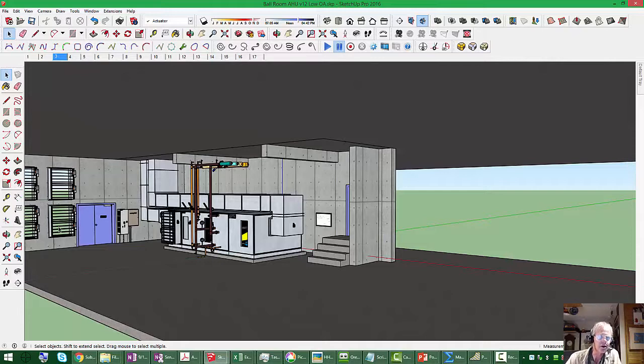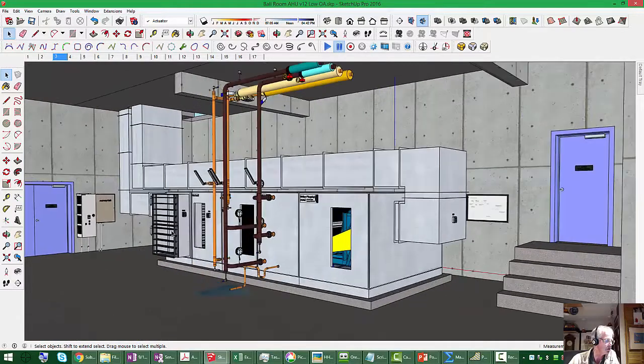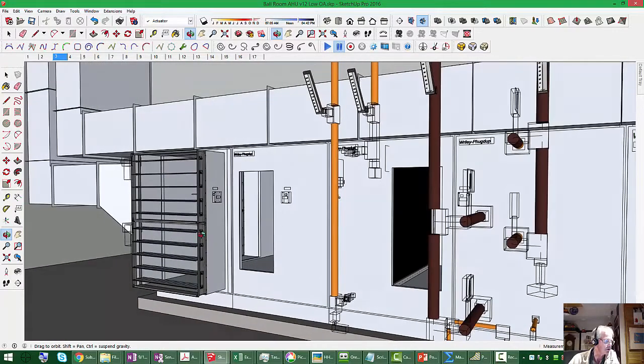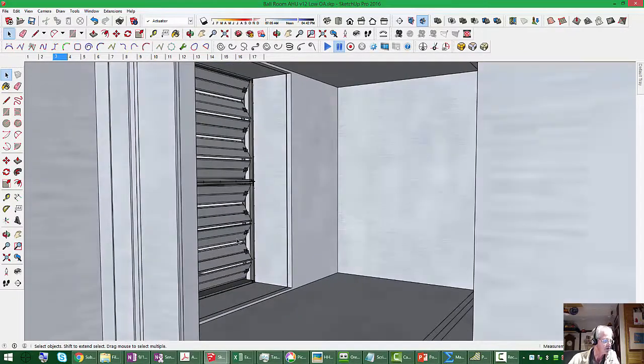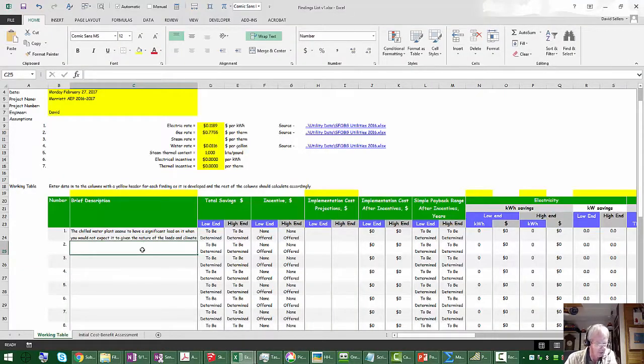Relief air basically is air that you have to leave out of the building that you brought in to provide free cooling in the economizer process. So aside from leakage, the relief dampers ought to, in some ways, track what the outside air dampers are doing, especially on a constant volume system. So if the relief dampers are wide open, you'd expect that to be happening because the outside air dampers are wide open. But if we go back here and take a look, and we can sort of do it as if we were looking in a door here, clearly the outdoor air dampers aren't wide open. So we have something else to put on our finding list, right? So this is AHU2.